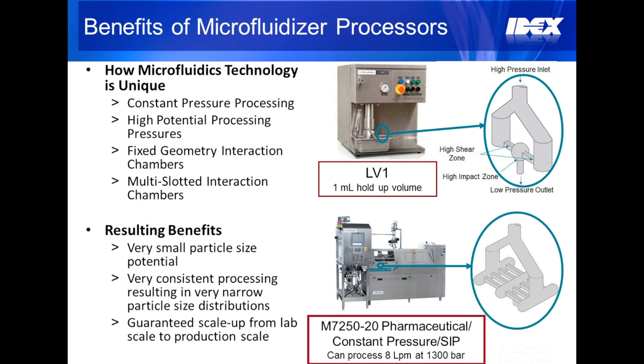Here is a summary of the key features and benefits of our technology. The microfluidizer processor offers constant pressure processing with a very high processing potential, up to 30,000 PSI. Our core technology is the fixed geometry interaction chamber, and multi-slotted interaction chambers are available for scaling up. These features result in a very small particle size potential, consistent processing with very narrow particle size distribution, and guaranteed scalability from lab to production scale.